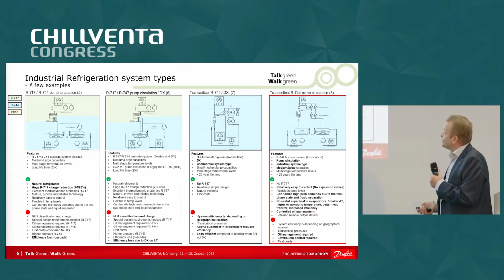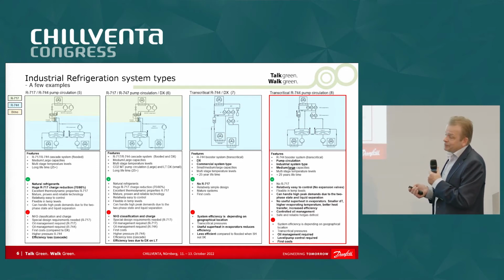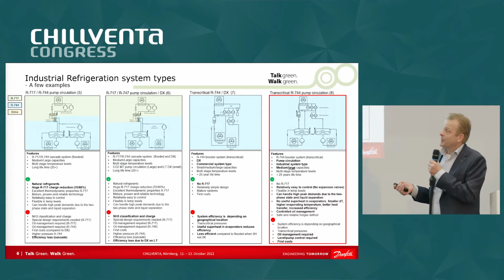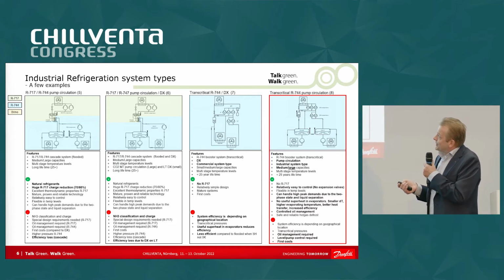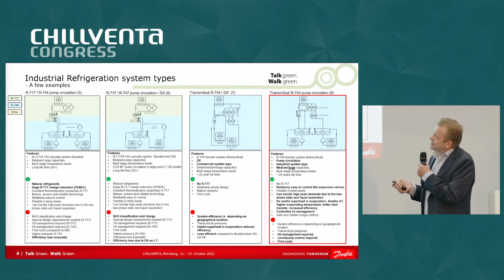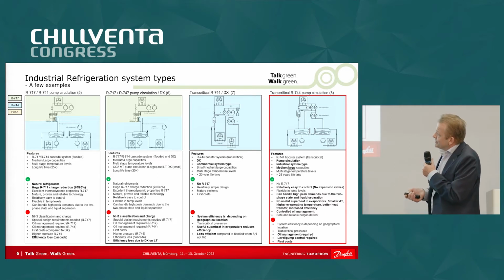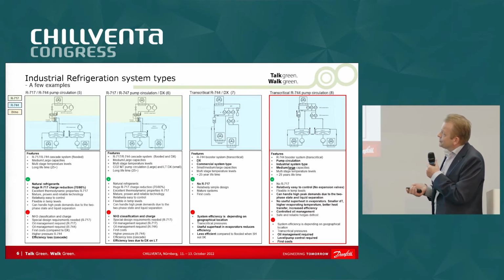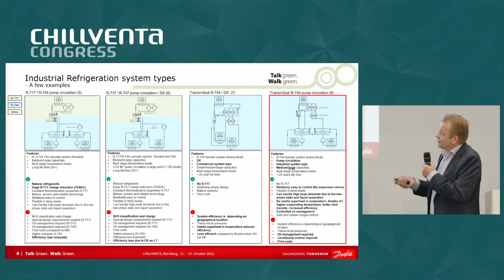Now we go to another interesting one. Ammonia on top and everything below is CO2, flooded systems. It's relatively simple to build, but of course you still have the cascade heat exchanger here. So the only downside, I would say, is that you have the efficiency loss here because of the heat exchanger. But for the rest, the way of building it looks like ammonia.